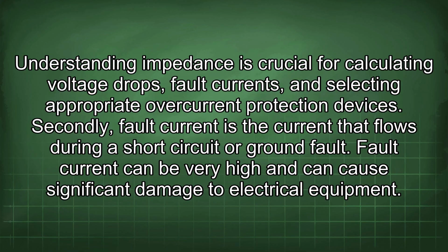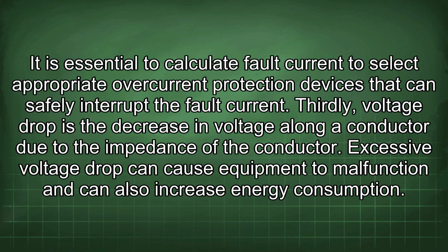Secondly, fault current is the current that flows during a short circuit or ground fault. Fault current can be very high and can cause significant damage to electrical equipment. It is essential to calculate fault current to select appropriate overcurrent protection devices that can safely interrupt the fault current.